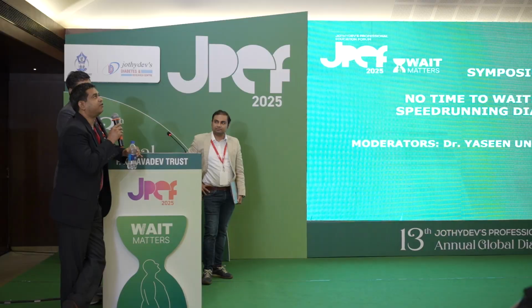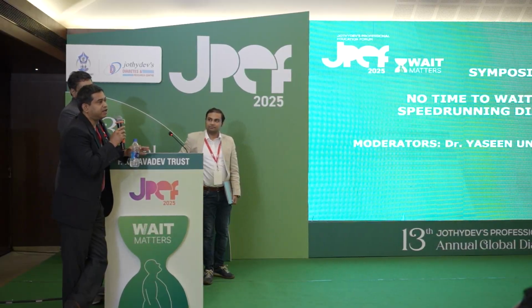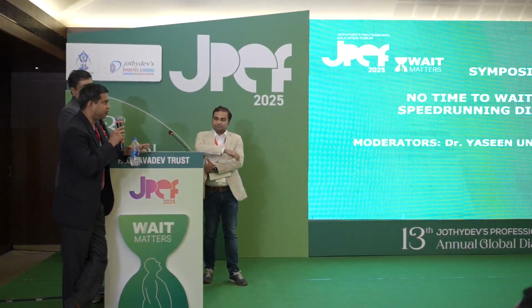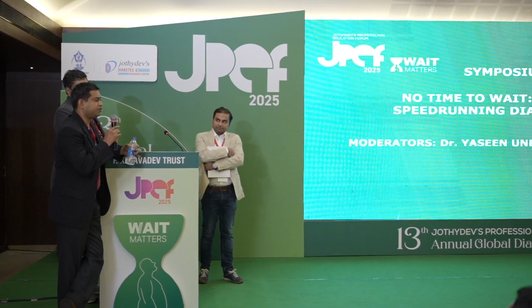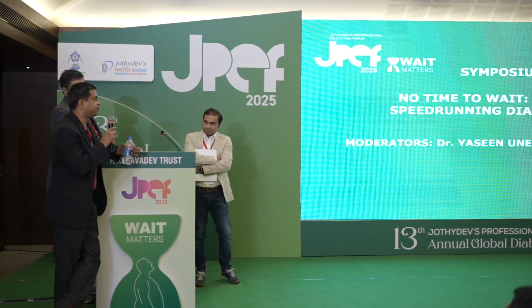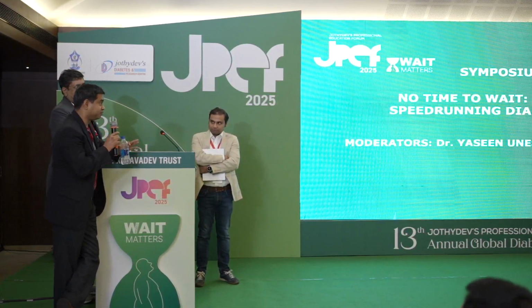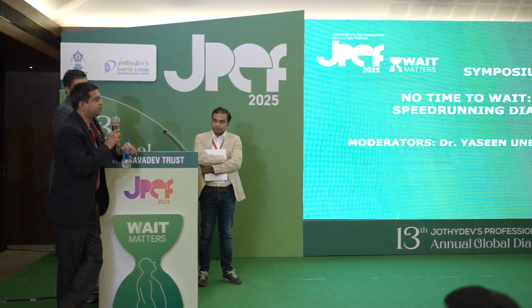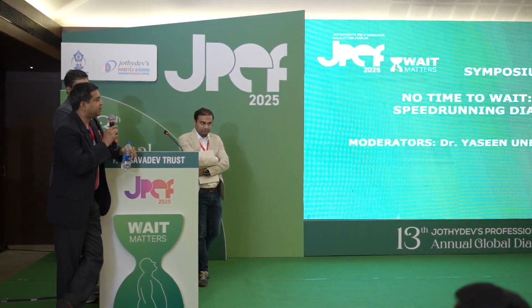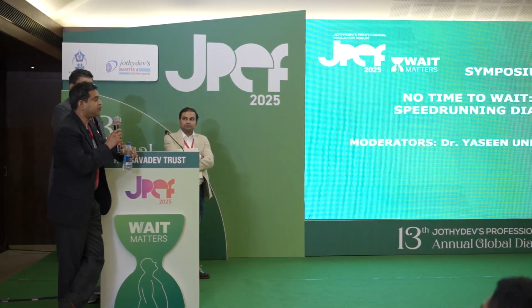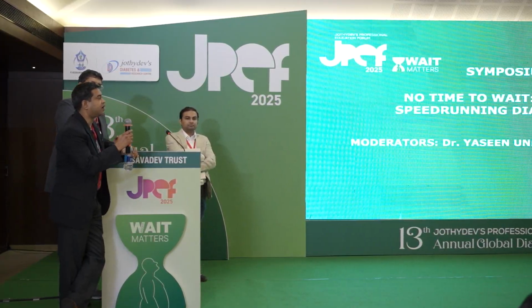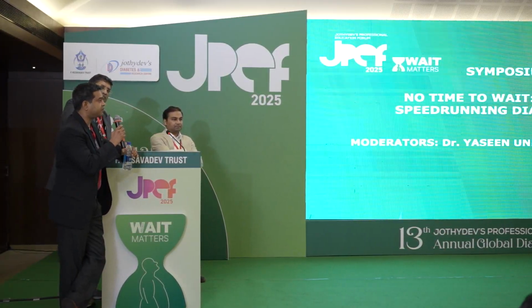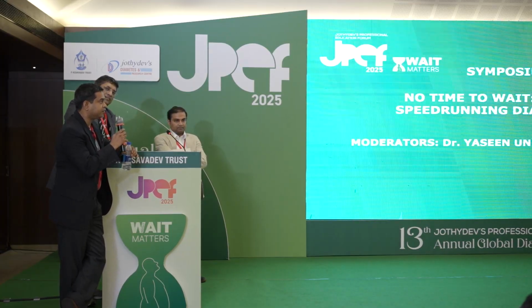So I have evaluated in my last 10 years, I think 5 projects on insulin pumps, 2 came for AID and I think 10 of them for non-invasive CGM. Are they coming in the market soon? No. They all failed in the initial clinical validation only. The first challenge for non-invasive CGM is your skin color, skin temperature, sweat, thickness of the skin.